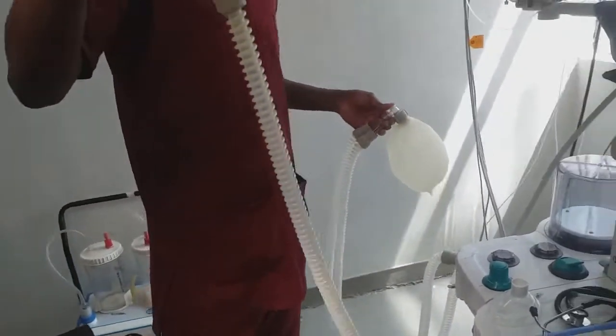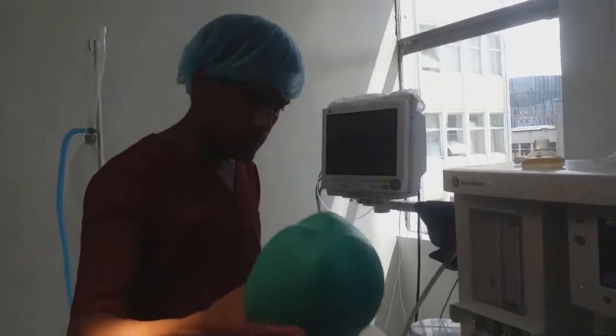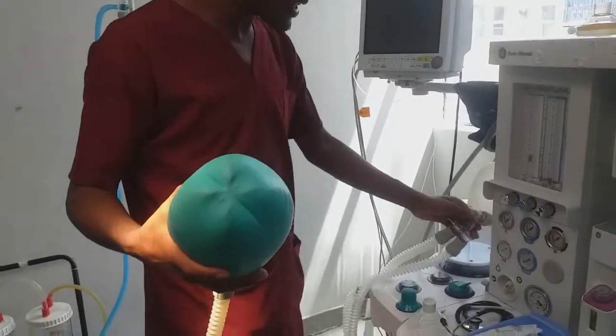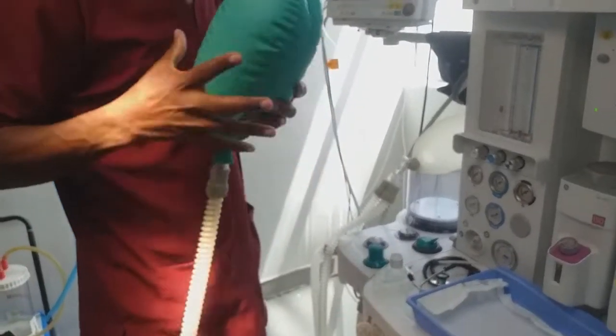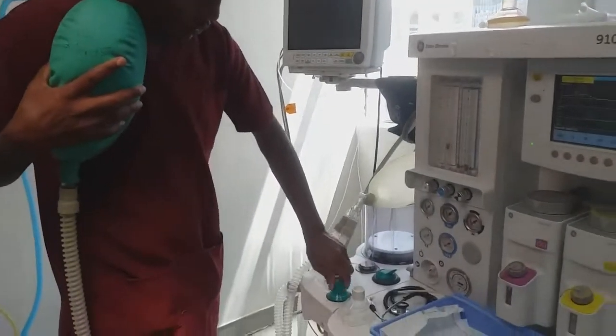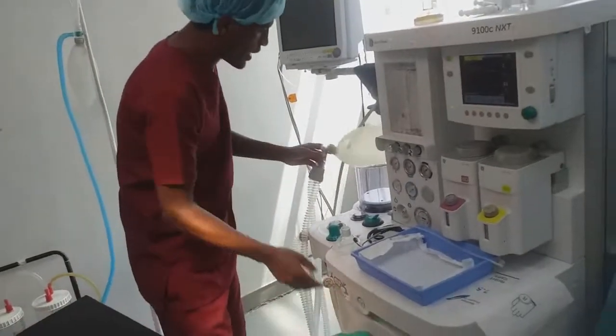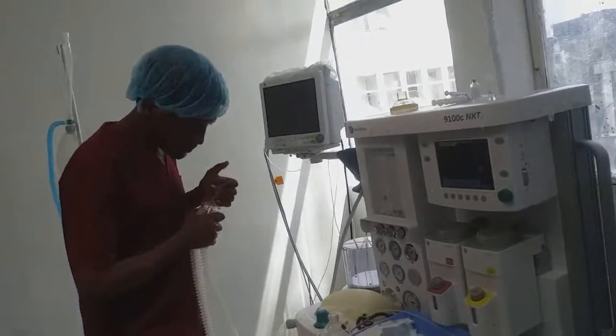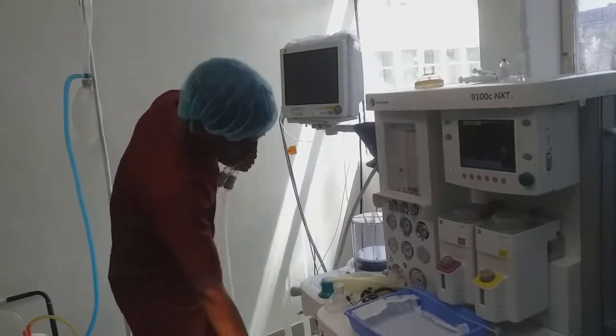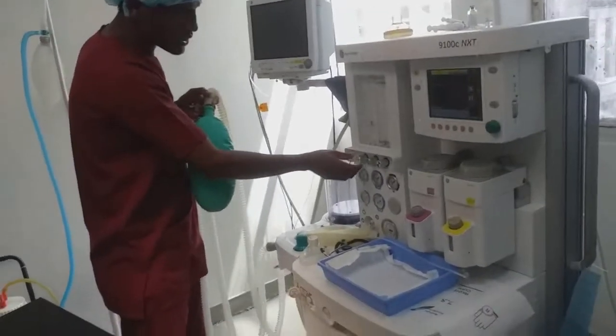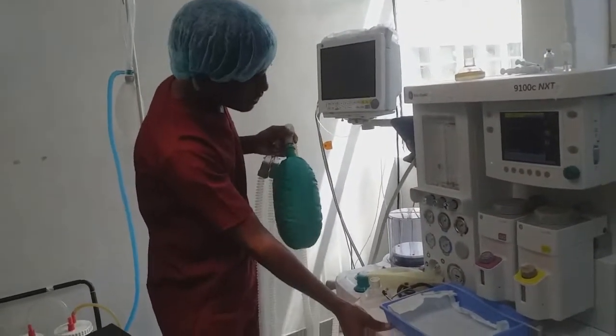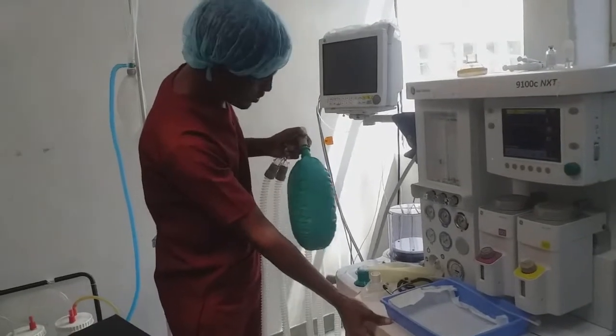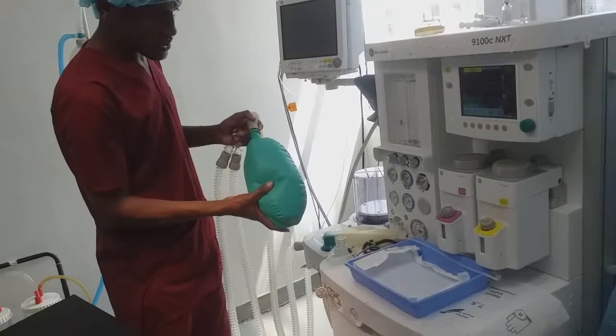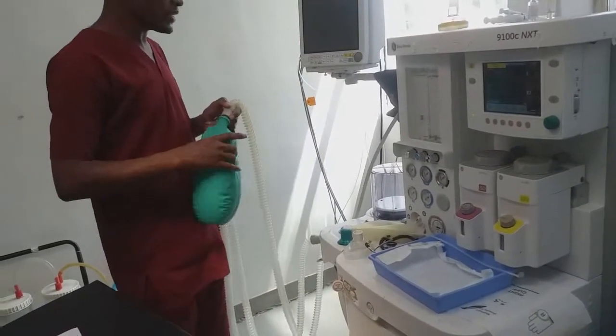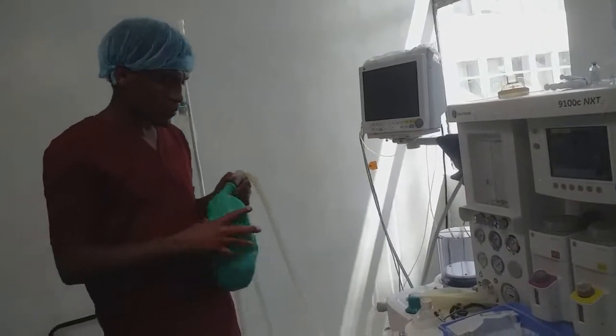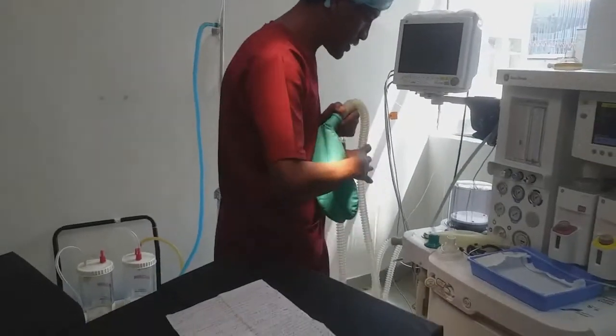We can also check the leak test for the bag ventilation system. I'm going to close the APL lever. Then I open the Y piece, and I open this pressure, oxygen up to 5. Then by flush, here there is no leak. This is the ventilation system check, just like this.